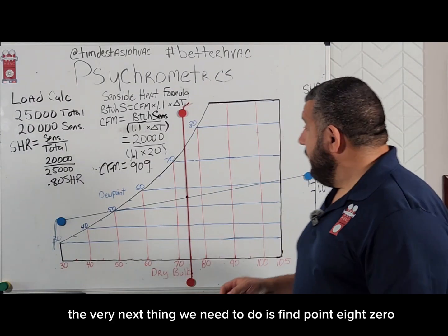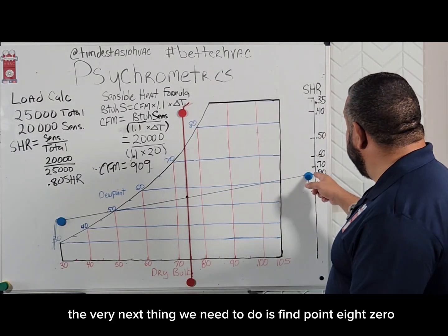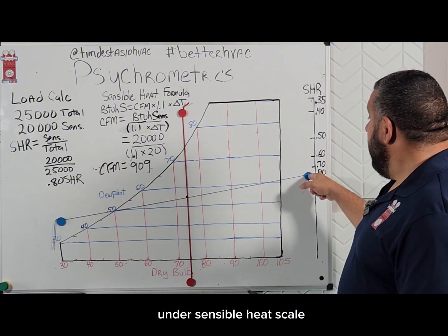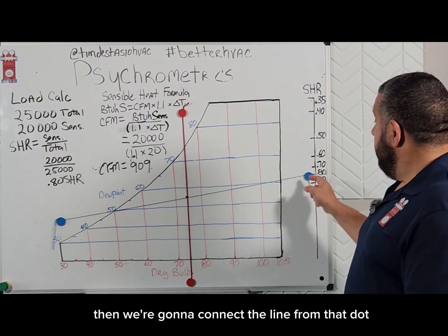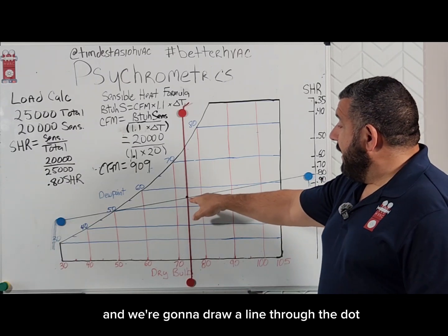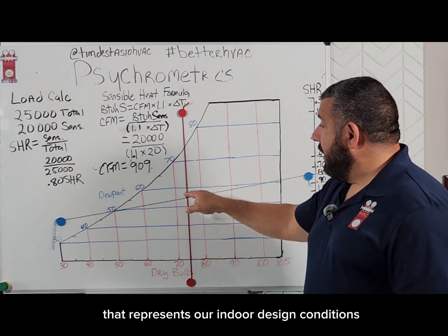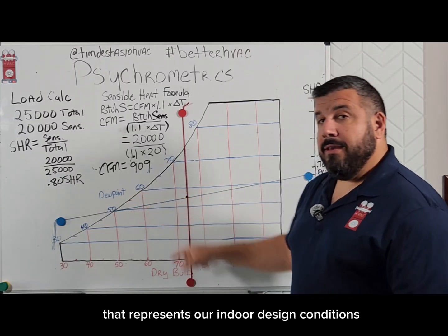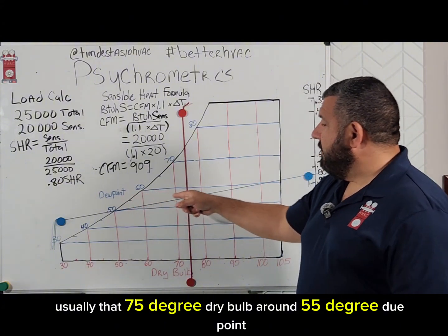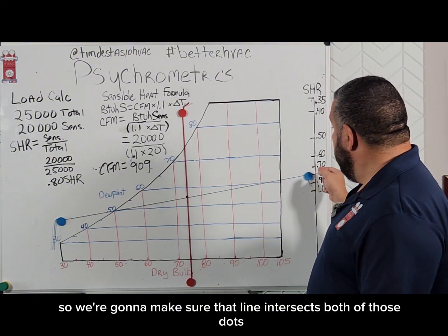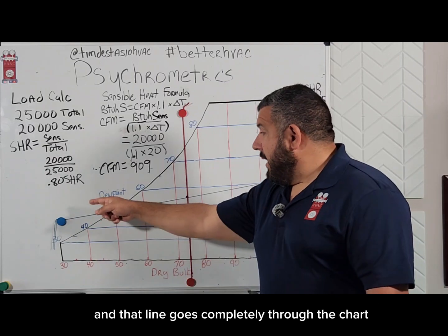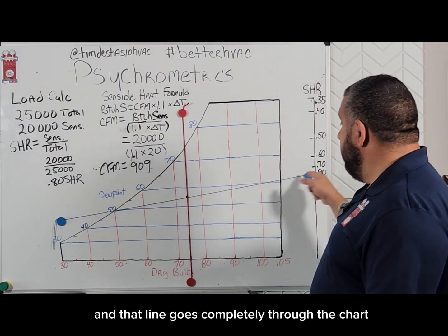What do we do with that? We find 0.80 on our sensible heat scale and draw a dot right there. Then we connect a line from that dot and draw it through the dot that represents our indoor design conditions — usually 75°F dry bulb, around 55°F dew point — making sure that line intersects both dots and goes completely through the chart.